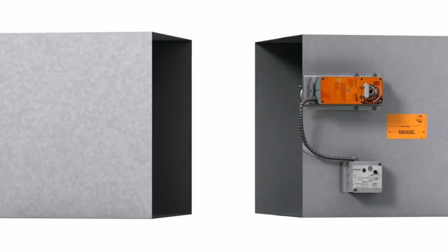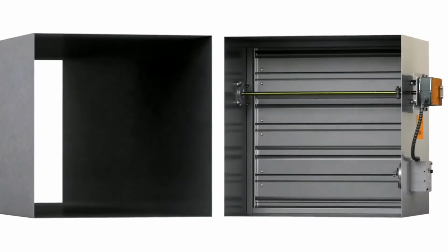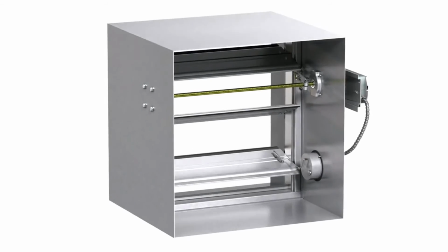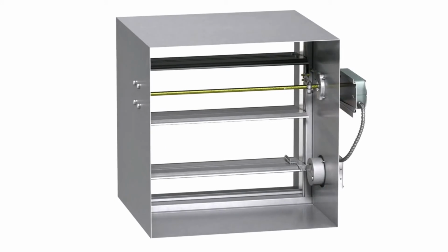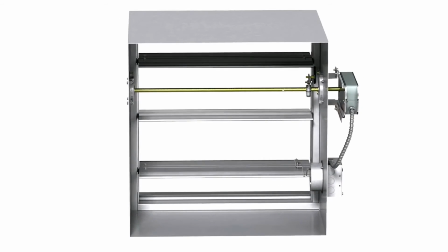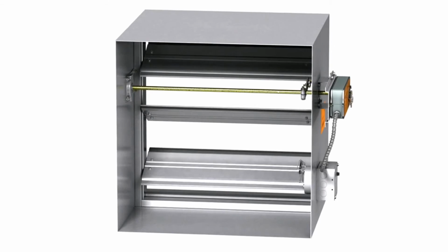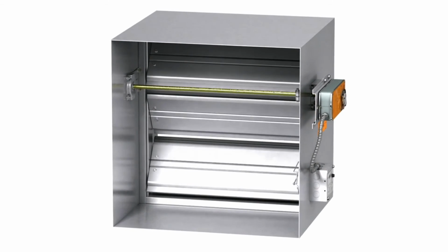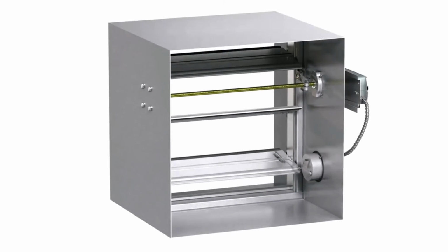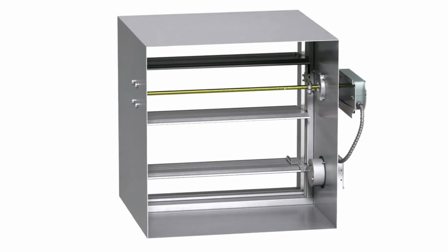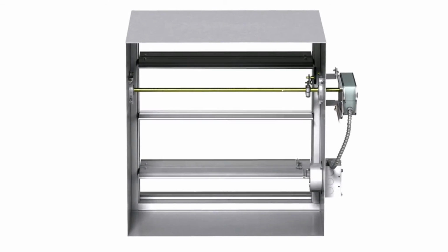All fire and smoke dampers must be installed in a steel sleeve which has a thickness equal to the connected duct gauge thickness but not less than 26 gauge. This steel sleeve is normally factory supplied with the damper to minimize the installation cost and to ensure that the required damper to sleeve fastening requirements are properly met.